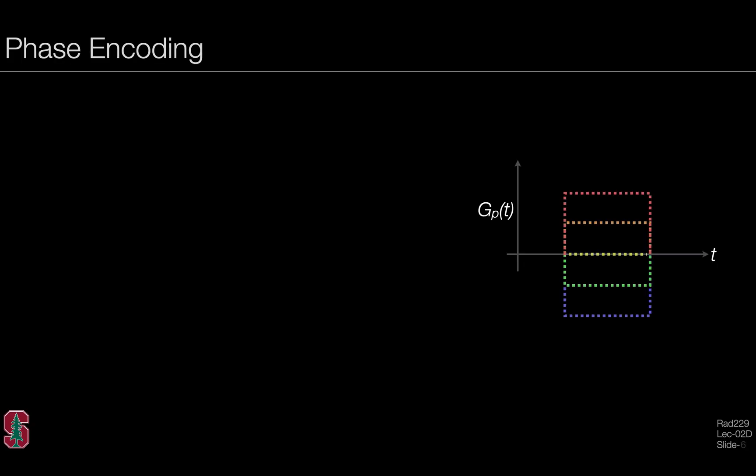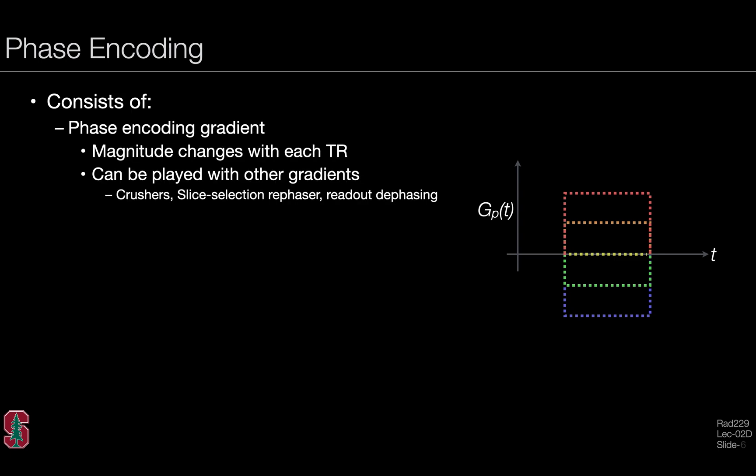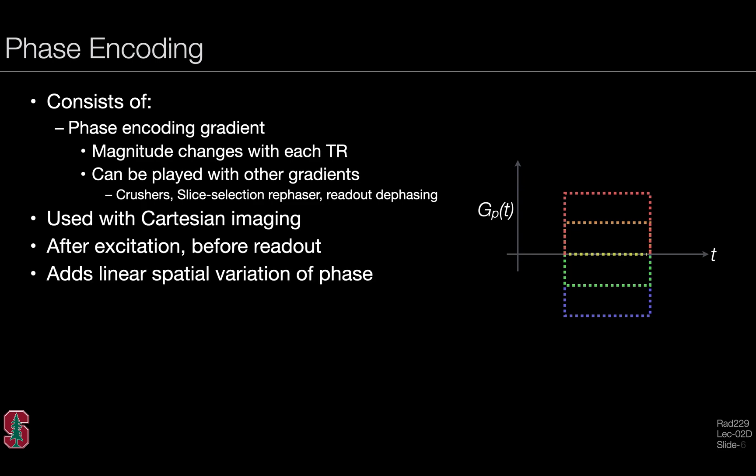Phase encoding consists of a phase encoding gradient, which is typically of a magnitude that changes with each TR. It can be played out with other gradients, which include things like crushers, slice selection rephasers, or readout dephasing gradients. Here on the right-hand side is a diagram of five phase encoding steps, going from a high positive encoding gradient to a low negative encoding gradient. This is conventionally used with Cartesian imaging, and it occurs after excitation, after the slice has been excited, but before readout, before the data is acquired. It adds a linear spatial variation of phase across the image. You can do phase encoding in one direction for two-dimensional imaging, or if you excite a fixed slab, you can use phase encoding in two directions for true inherent three-dimensional imaging.